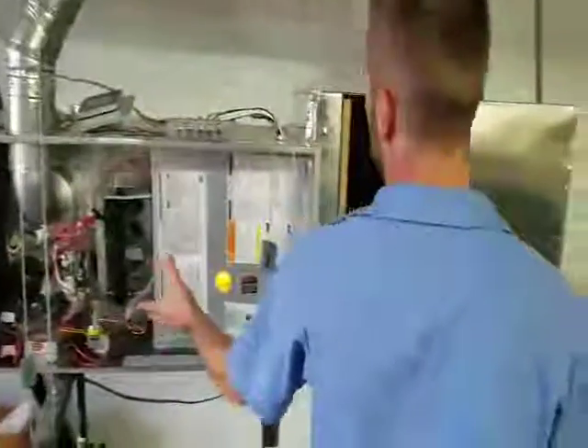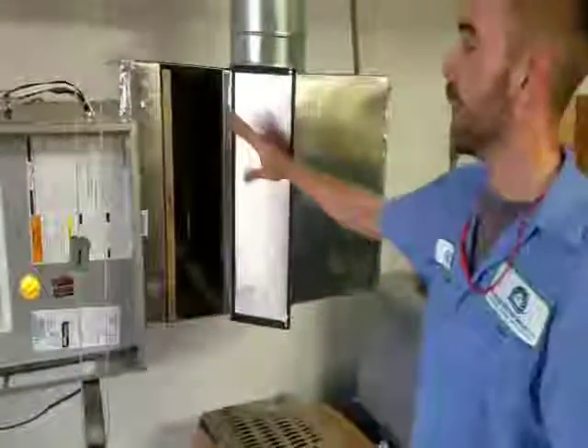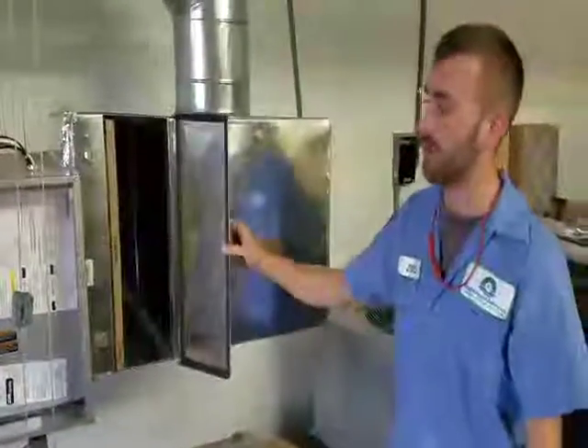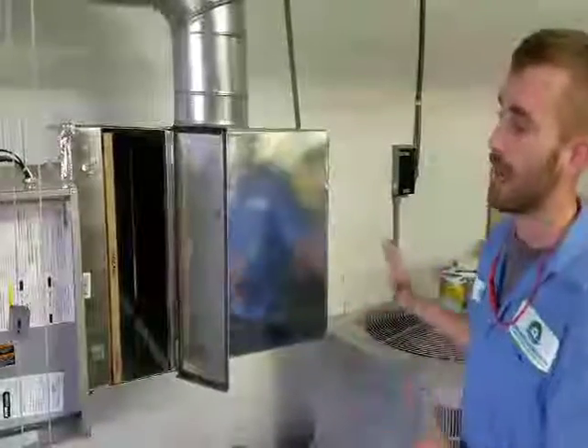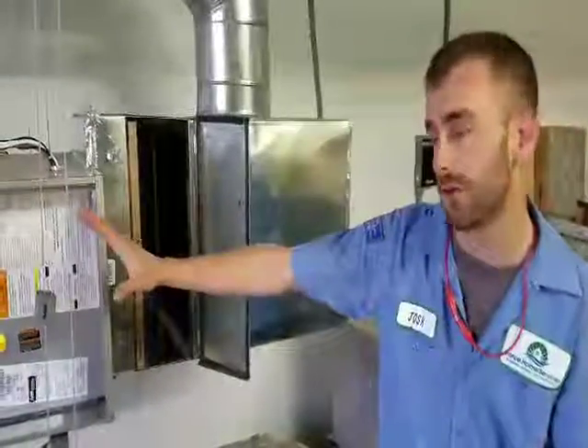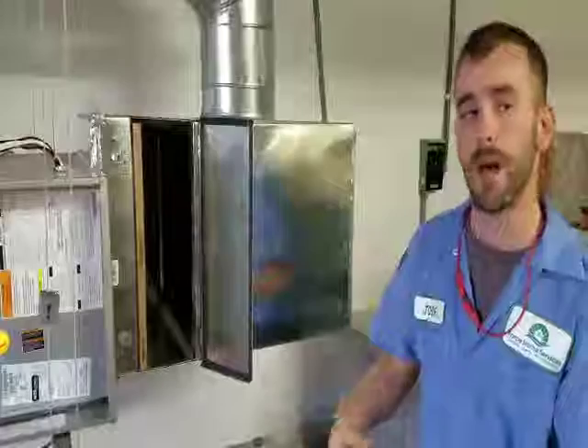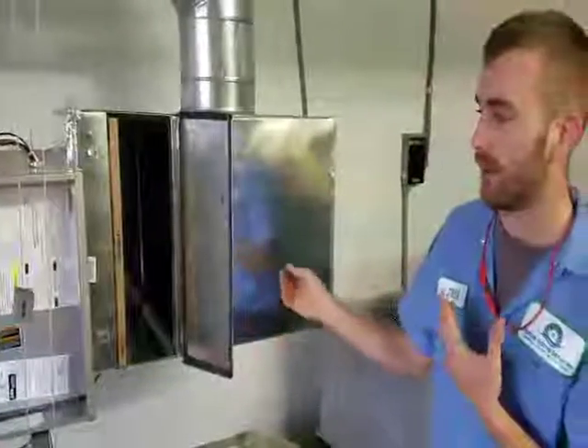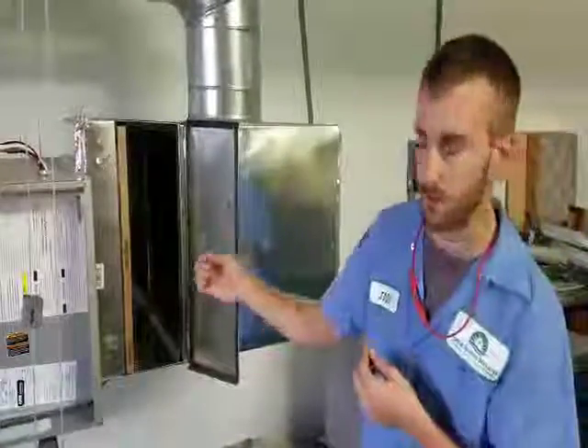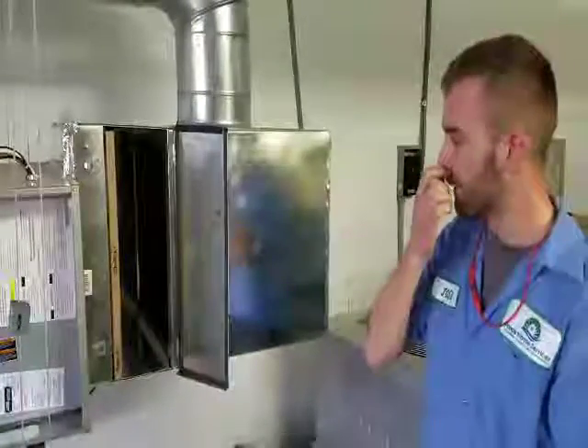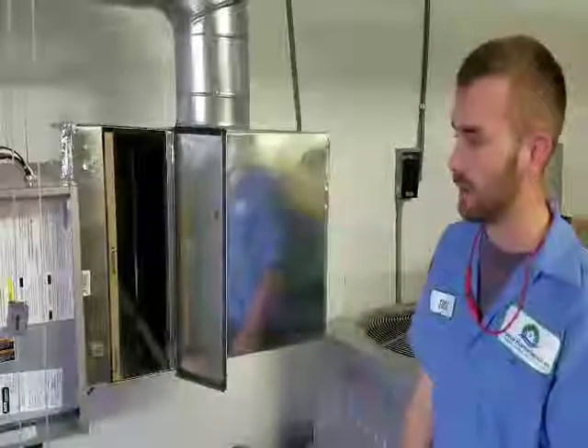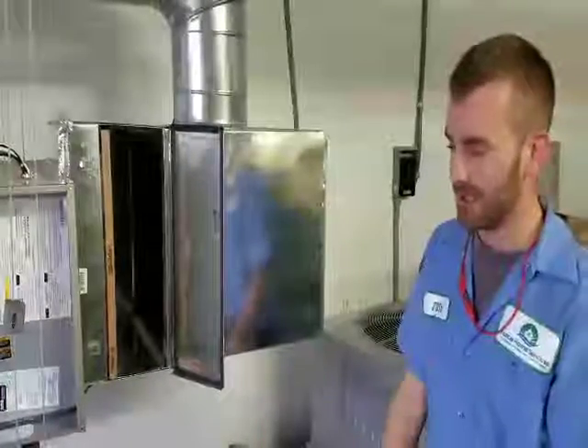A lot of the reasons behind cracked heat exchangers come back to poor airflow. If your system is struggling to pull air, or it can't get enough air across the heat exchanger, that's going to cause the metal to overheat and expand, and then it will crack either at the weld or at the little back end joint. So that's something you definitely want to take precautions against.